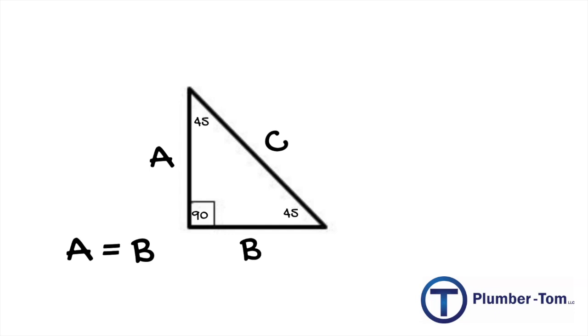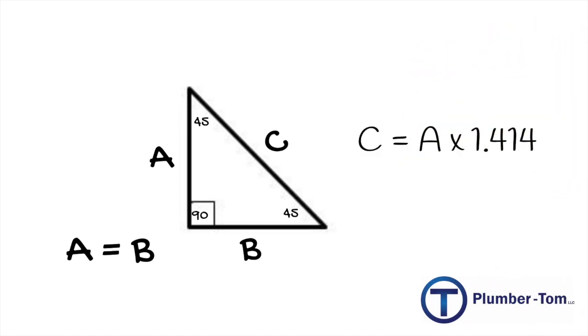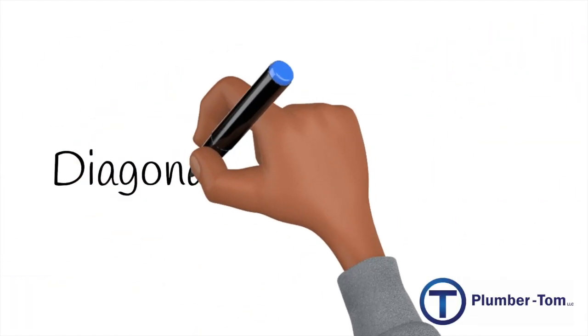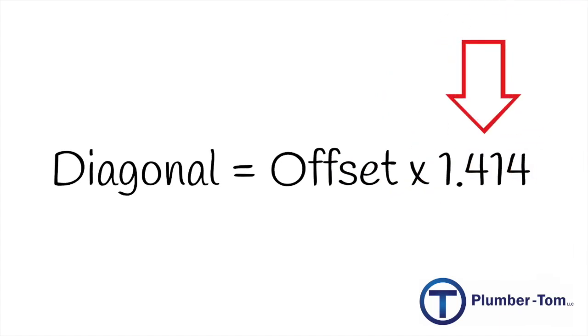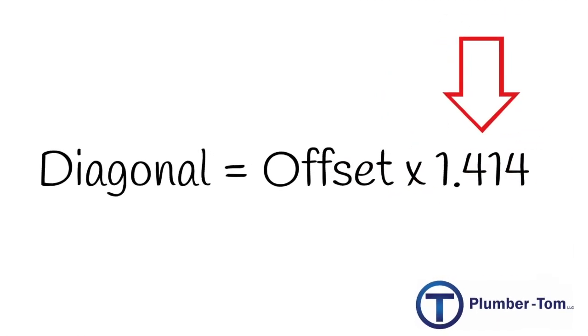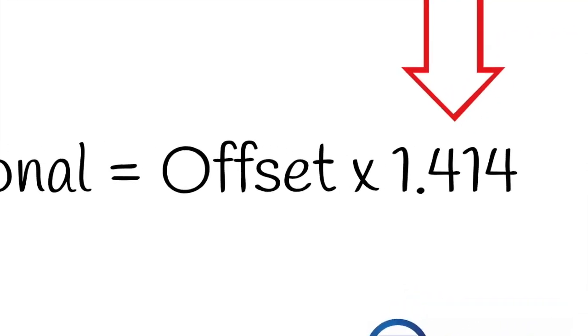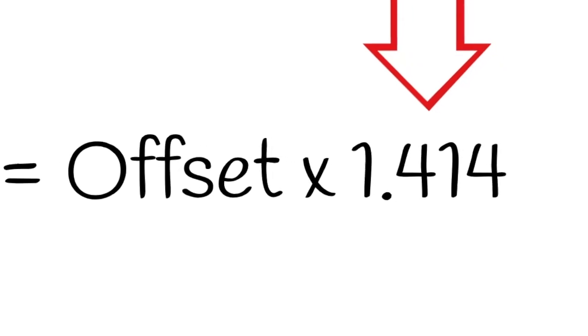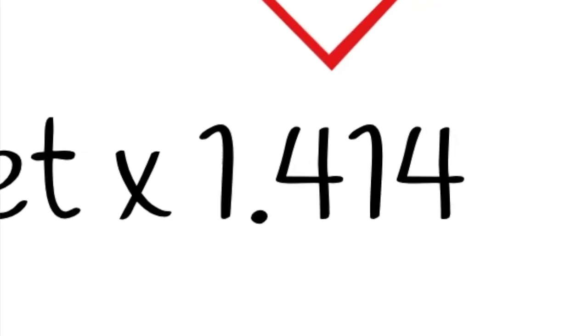Most often, we are calculating for the diagonal, which is C, because that's where the pipe will run. To calculate C, we must simply multiply the offset by our magical plumber number, 1.414. If you are a plumber, if you intend to be a plumber, this is a number that must be burned into your mind and memory forever. 1.414.